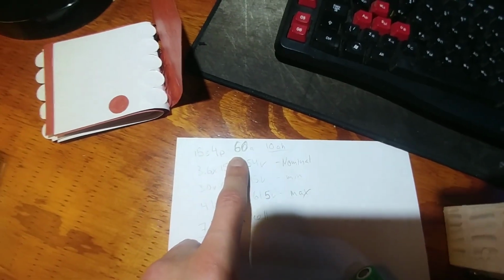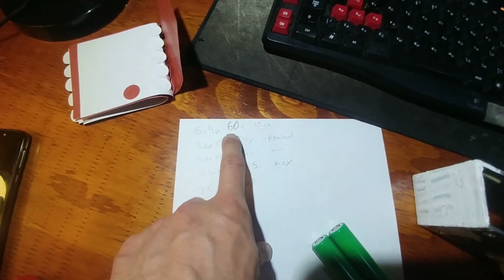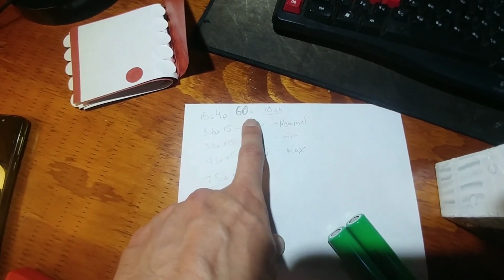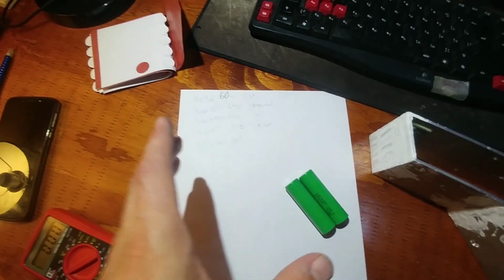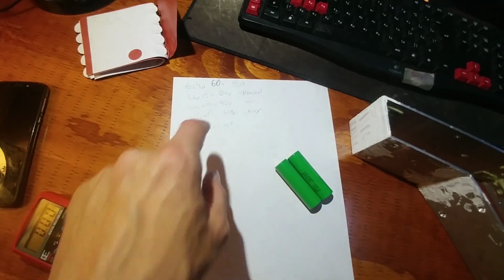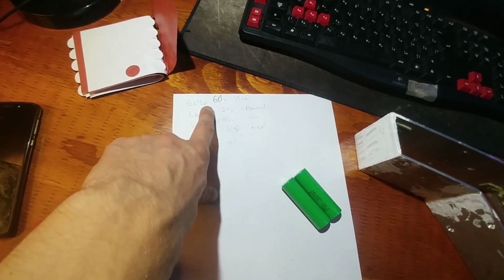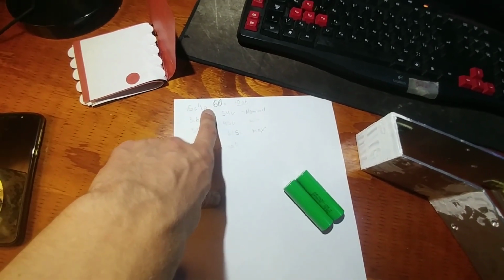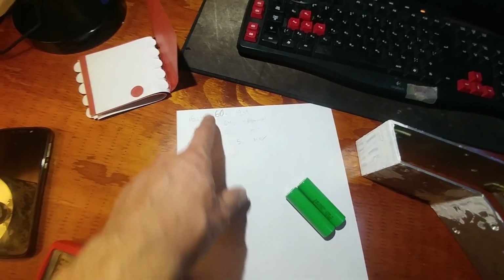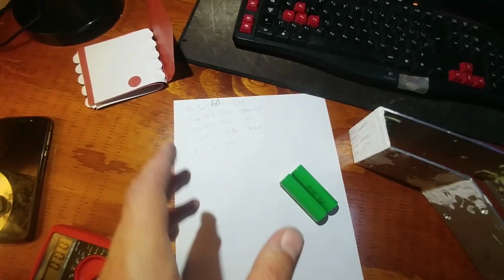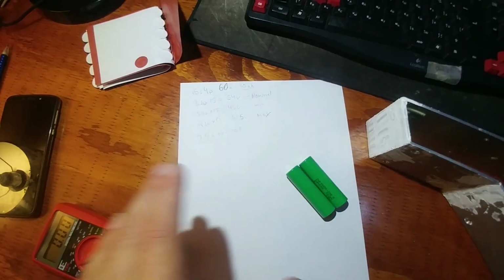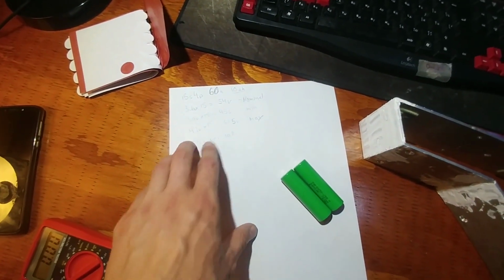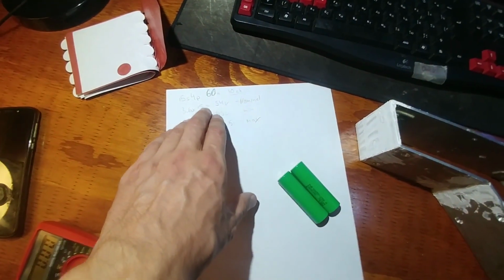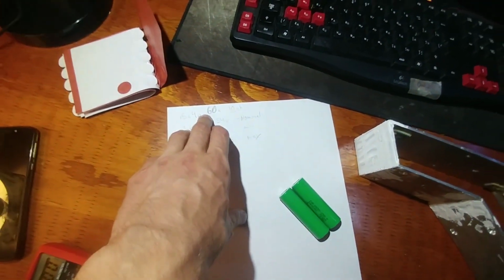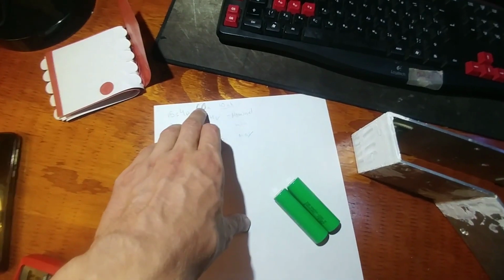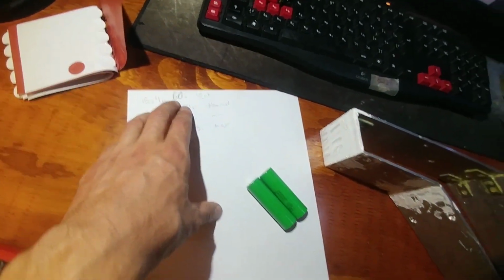I'm also going to talk about the 60 amp rating. I am going to build this battery to be able to put out 60 amps safely, but there's no way I will ever draw this much out of the battery. I'll only be drawing 20 to 30 amps. The reason I'm going to 60 is to have some safety factor, so in case something were to go wrong, I'm always safe. Even if I draw more than 20 or 30 amps, I'm still safe because the battery is built for 60.